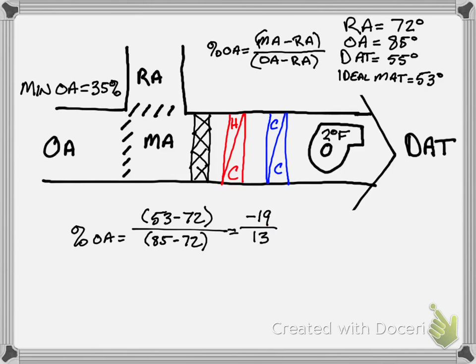Now right away we can see that we have a negative number on the top and a positive number on the bottom, and so we know we're going to come out to be a negative number, which ends up being negative 146%. Obviously this number isn't possible, but if we just look at the minimum and maximum, this is less than the 35% minimum that this air handler is capable of. So we're not able to meet our desired mixed air temperature at this scenario.